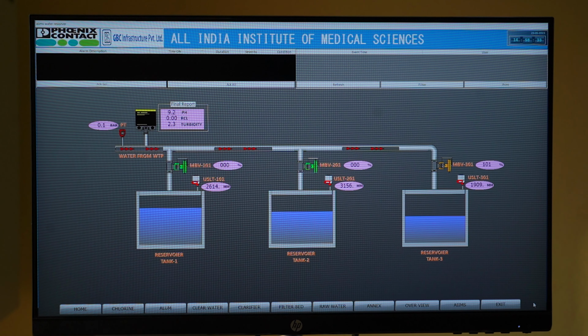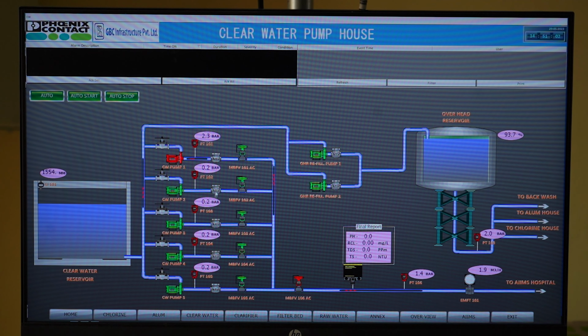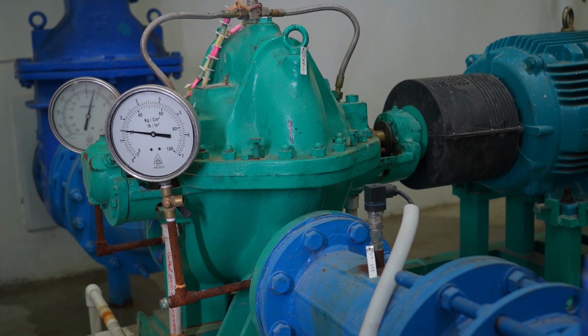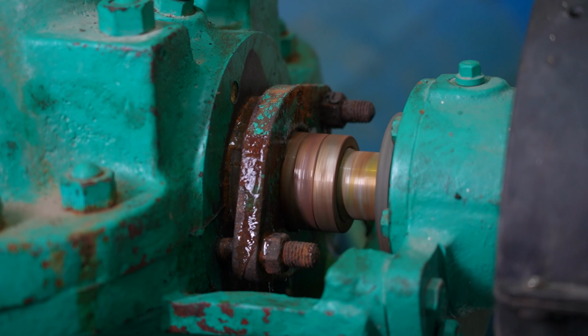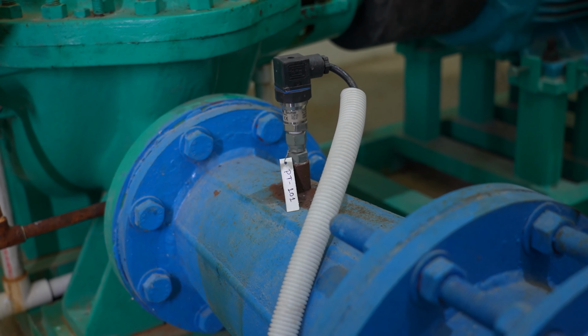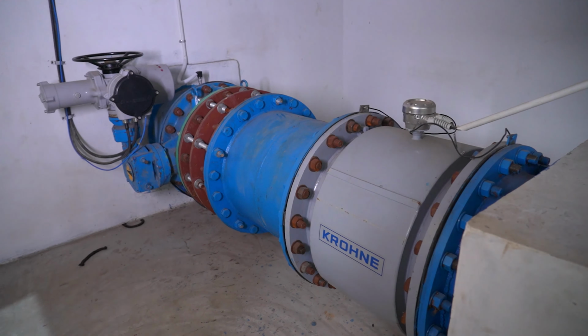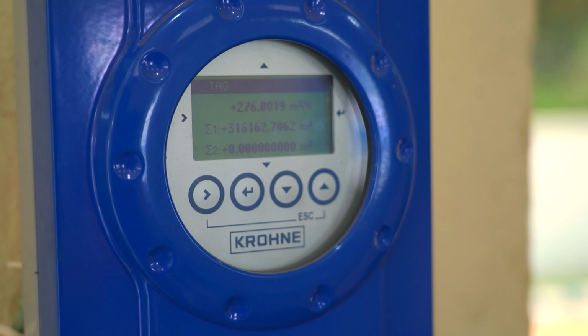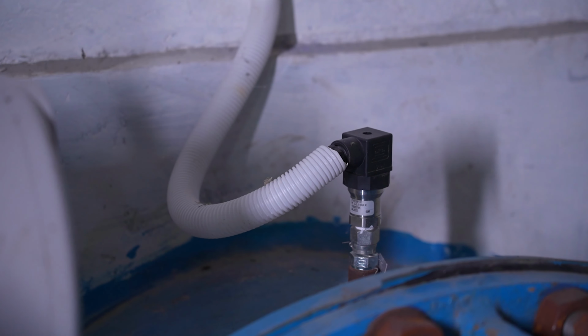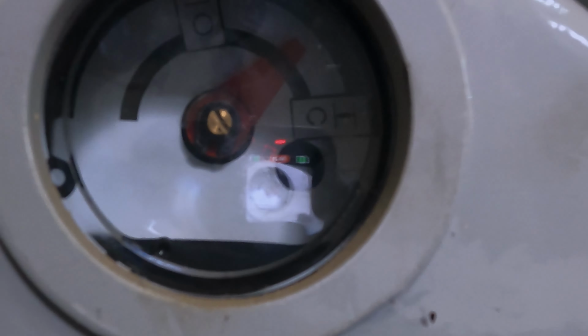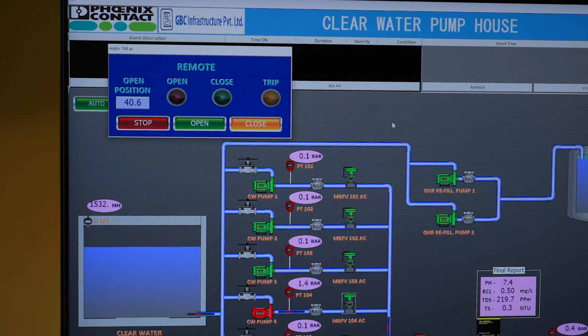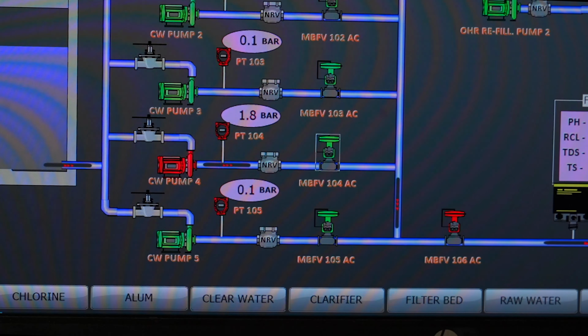Now, the operator, after watching the levels of tanks at AIIMS hospital compound, decides to start the delivery pump at the clear water pump house by just clicking a few buttons of the mouse. The health of the running pumps is monitored from the feedback of the sensors attached to the pumps. The rate of final output flow through the common delivery line and the pressure of the final outgoing water in the delivery line are monitored by an electromagnetic flow meter and a pressure transducer respectively, and adjusted accordingly as per requirements.